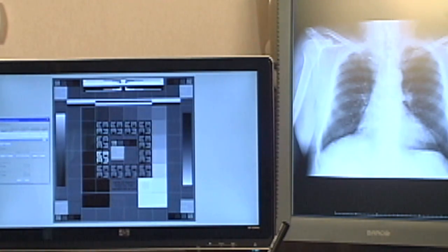And another question, Ken, if there's sometimes a software issue, and I understand sometimes there might be different lookup tables or different processing that can be applied by the vendors of the PACS systems. So when we want to make sure that we identify those issues as well, we don't necessarily want to take the image that's available on the monitor by the vendor, but go early in the pipeline, correct? That's true.